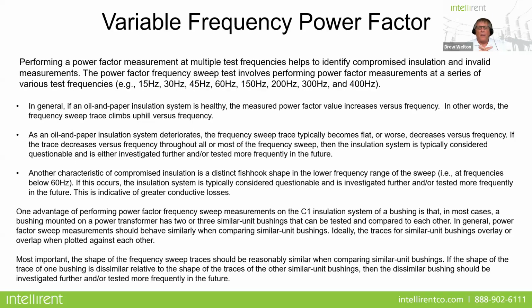So, one of the things that I want to bring to light, and I think this is very, very important and something that really gets overlooked, because I know it gets overlooked because I rent test equipment. And when I see people rent various types of test equipment that can only do power factor at 60 hertz, I know we're missing the ball on this technology. This is also very applicable to doing power factor testing on a transformer as well.